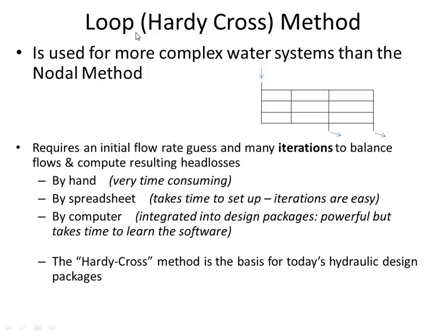If there's a certain flow path that has a really big R, that means either that there's a high friction factor, long length, or small diameter. So less water is going to go through a route that has a high R than a route that has a small R. And so that can help you in making that initial guess of what the flow rates might be.